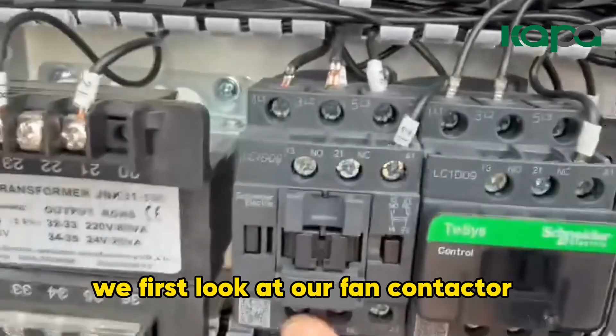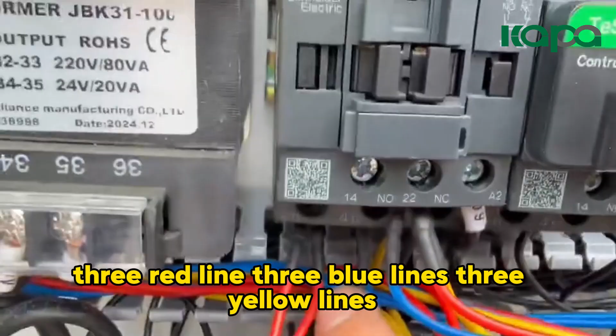Now, when we change our 220 wiring to 480 volts, we first look at our fan contactor. There are a total of 9 lines under this fan contactor: 3 red lines, 3 blue lines, 3 yellow lines. So the first step to get 480 volts: let's first look at the lower terminals here. There is T1, T2, T3.